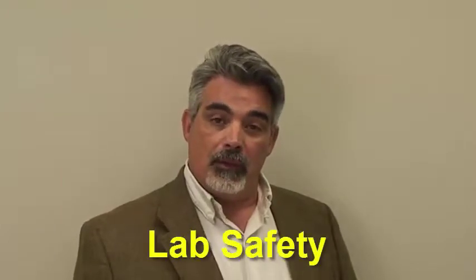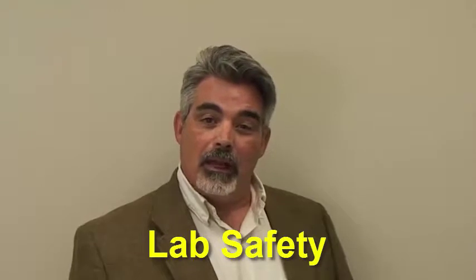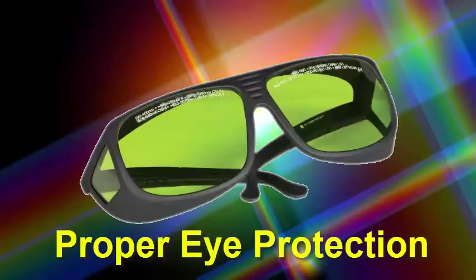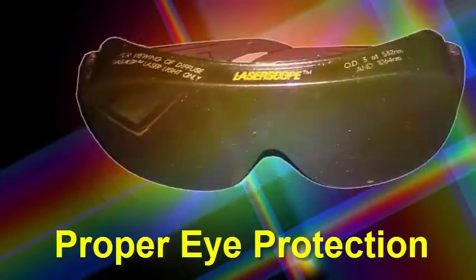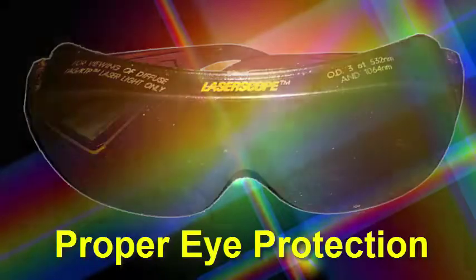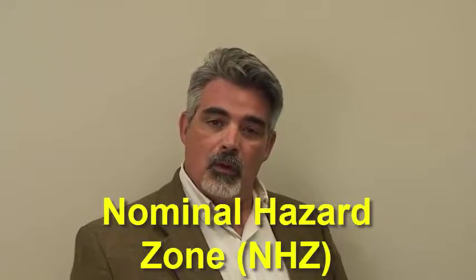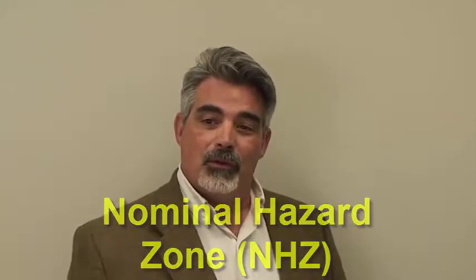One of the first things we want to talk about is lab safety. You will be working with high energy lasers and want to make sure that we are being diligent in using eye protection. This eye protection that you use will be wavelength specific, so make sure that you're matching your eyewear with the laser wavelength that you're using. You also want to pay attention to your maximum permissible exposure as well as your nominal hazard zones.